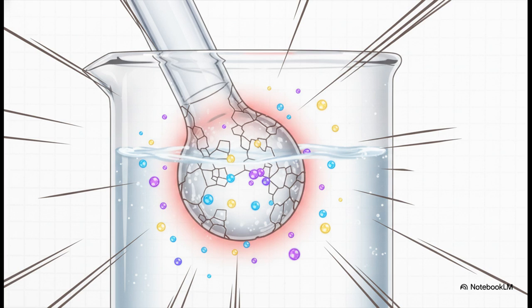Listen up, because this is crucial. Never, ever store your electrode in distilled or deionized water. Remember that delicate 50-nanometer hydrated layer we just talked about? Well, it needs ions to survive. If you dunk it into pure distilled water, those ions are just violently leached right out of the glass. The membrane dries out, the resistance skyrockets, and you end up with incredibly noisy, super inaccurate readings. Always use the proper storage solution for sure.